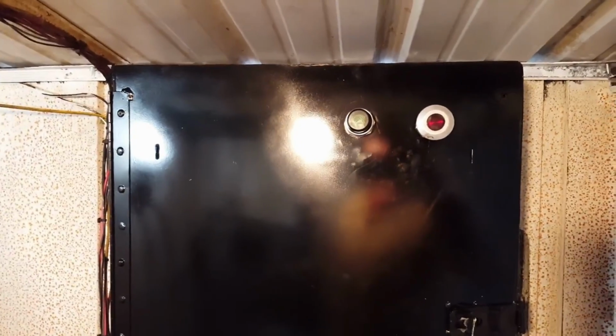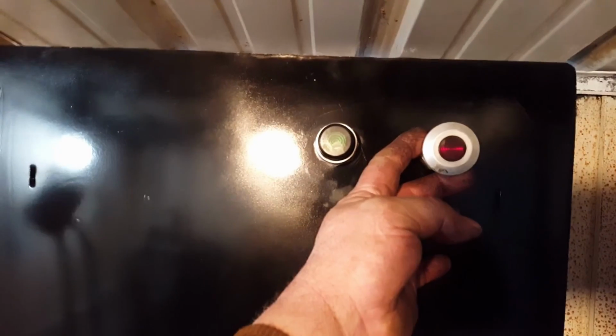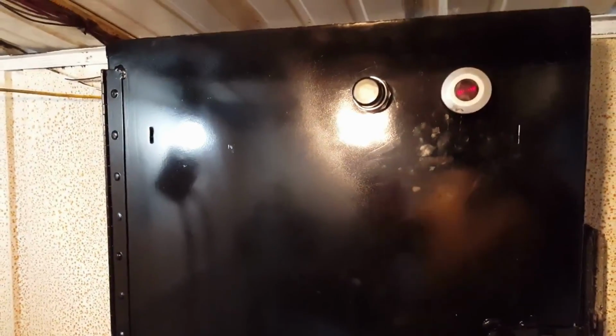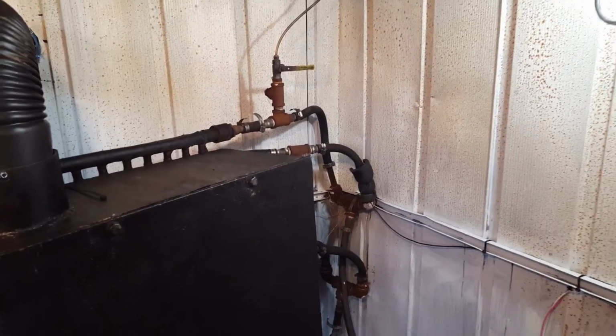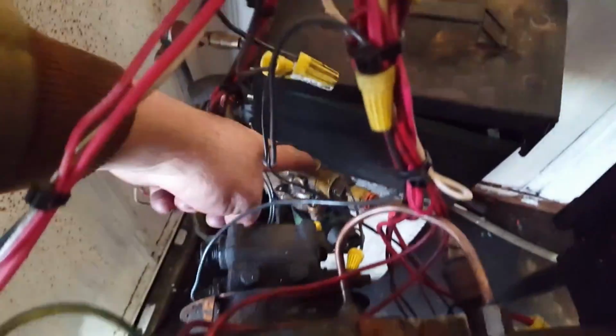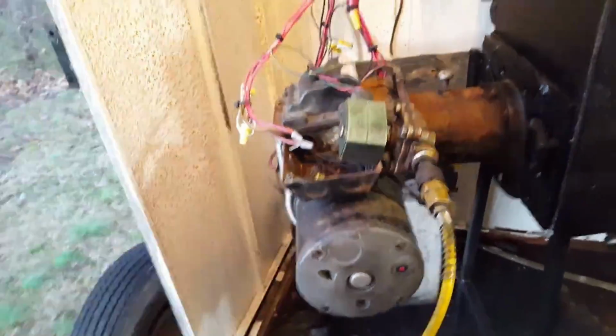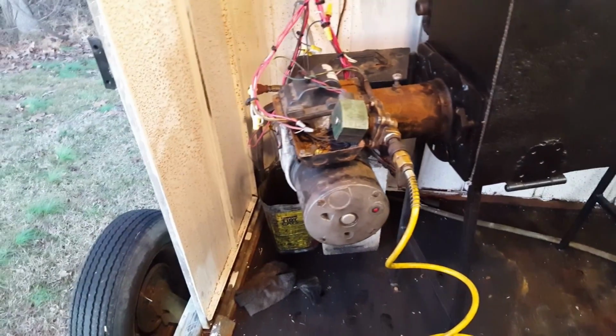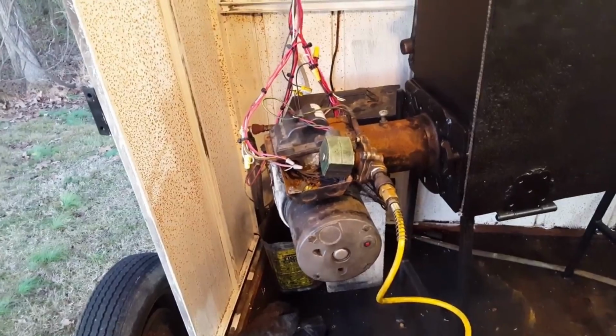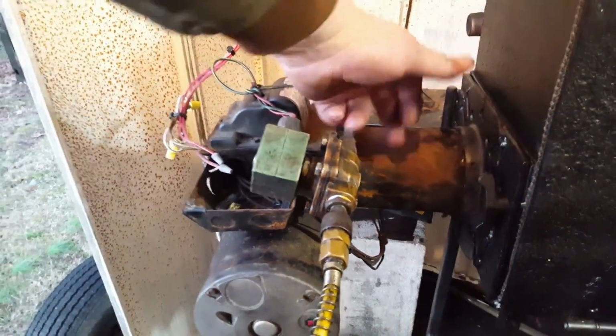All right, I'm going to run you through everything it needs to see, everything that needs to happen for this thing to run. Like I said, I got to pull the E-stop out, push the start. Then if it gets a call for heat from the thermostat, it'll send the signal to the PLC, and that starts the chain reaction. It has to have no signal from the over temp sensor. Then once the PLC is satisfied, it opens this valve, it opens this valve, it turns this blower motor on. And I think it's got 5 seconds to light. If it doesn't light in 5 seconds, it shuts down. That is done by the flame sensor in here.